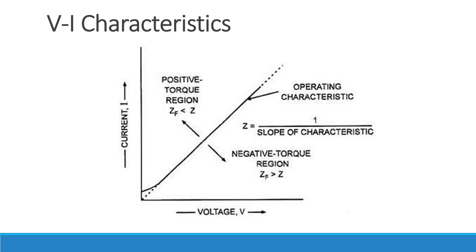Next we will observe the VI characteristics for this distance relay. On the x-axis you have the voltage and on the y-axis you have the current. The impedance is given by the straight line with a certain slope. Here you have the positive torque region, which is the region where the fault impedance is less than the setting impedance Z, and the negative torque region where the fault impedance is greater than the setting impedance Z. Whenever a fault occurs, the impedance on the line drops below the setting impedance, providing a positive torque and causing the relay to operate.